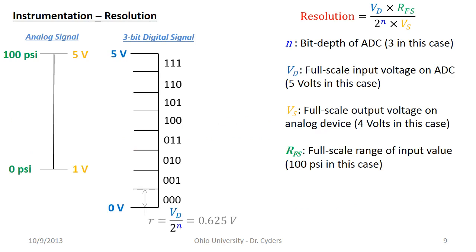What happens if the analog device's voltage range differs from the ADC's input range? Visually, we're not using some of the bits — we're not reading the full capability of our ADC to resolve the signal. Where before we were reading 0 to 100 psi over the entire 8-bin range, now we might only be dividing that range over 6 bins, reducing our resolution.